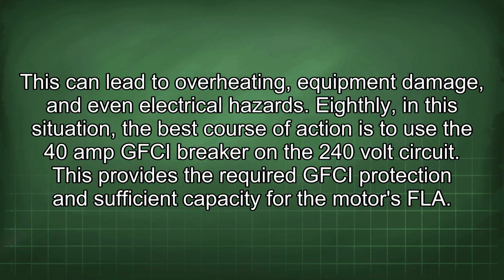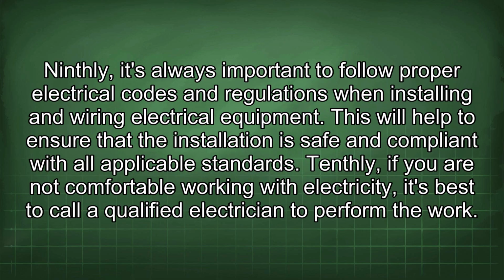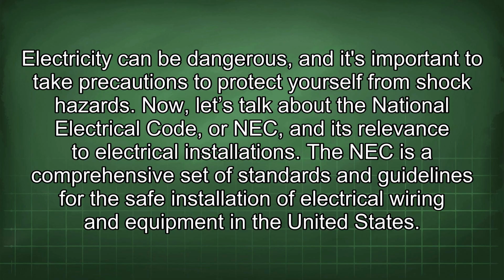Eighthly, in this situation, the best course of action is to use the 40 amp GFCI breaker on the 240 volt circuit. This provides the required GFCI protection and sufficient capacity for the motor's FLA. Ninthly, it's always important to follow proper electrical codes and regulations when installing and wiring electrical equipment. This will help to ensure that the installation is safe and compliant with all applicable standards. Tenthly, if you are not comfortable working with electricity, it's best to call a qualified electrician to perform the work. Electricity can be dangerous, and it's important to take precautions to protect yourself from shock hazards.